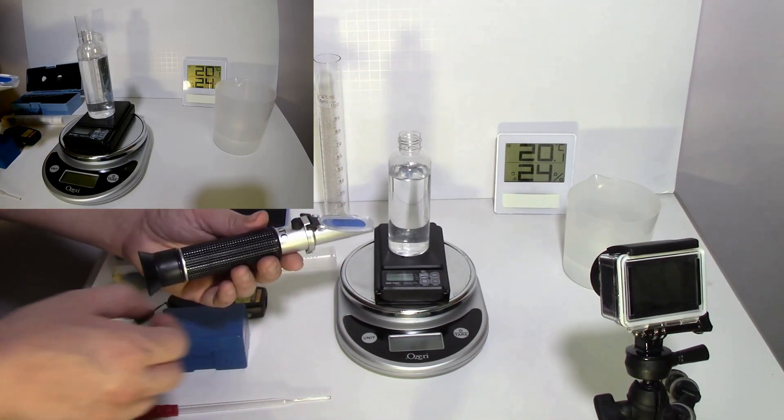Here is the refractometer. We'll get a still shot here. The GoPro knockoff did not like that. We're at zero, and that's how you calibrate this particular device.